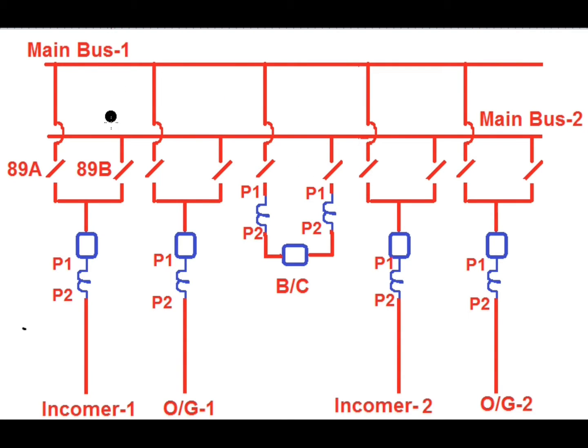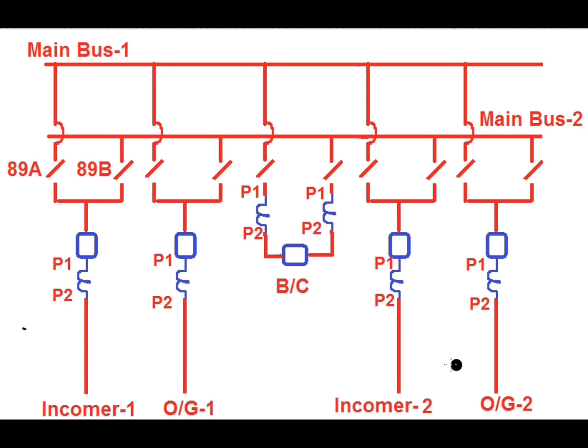Welcome back to the channel. Today I will discuss bus bar protection for a two-bus system and how the overlapping of the zone will cover faults occurring between the bus coupler CT and the bus coupler breaker. There exist two buses: main bus 1 and main bus 2, coupled by a bus coupler bay. In the bus coupler bay there exist two CTs — one connected towards main bus 1 and another towards main bus 2. There exist four feeders: two incomers and two outgoing feeders.